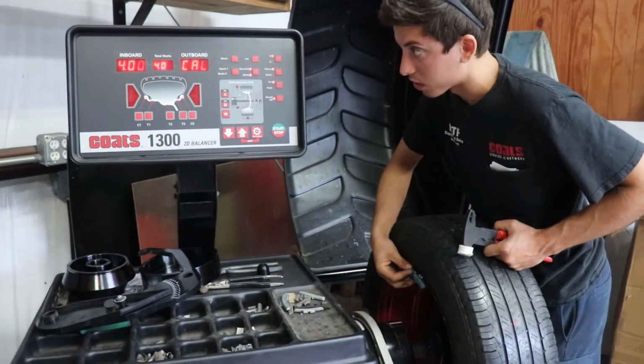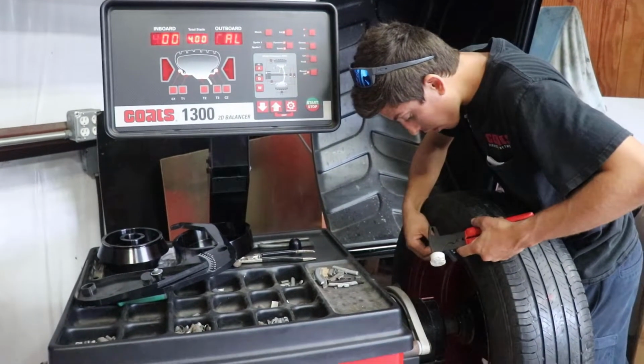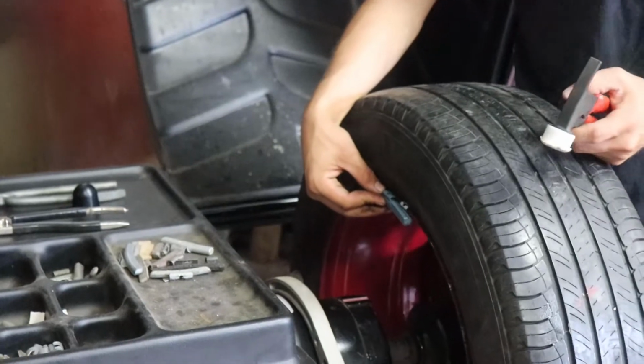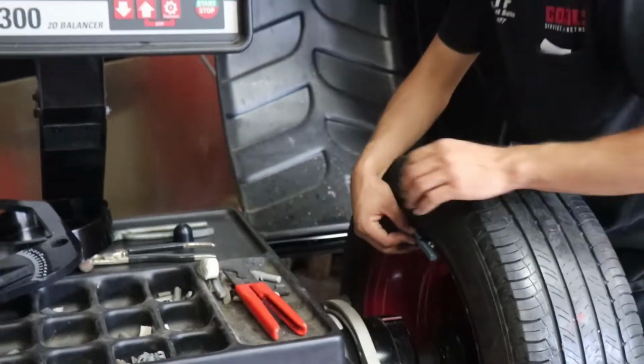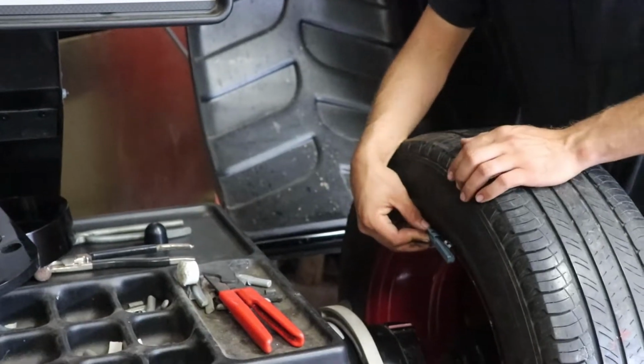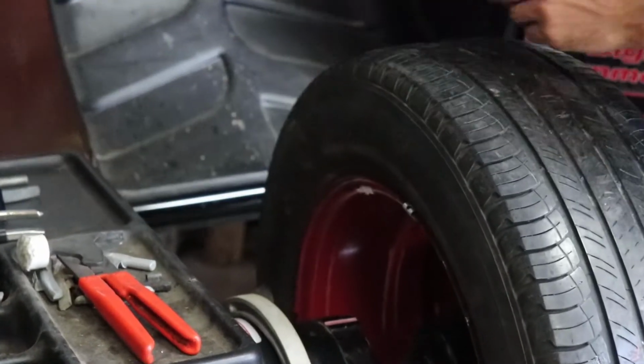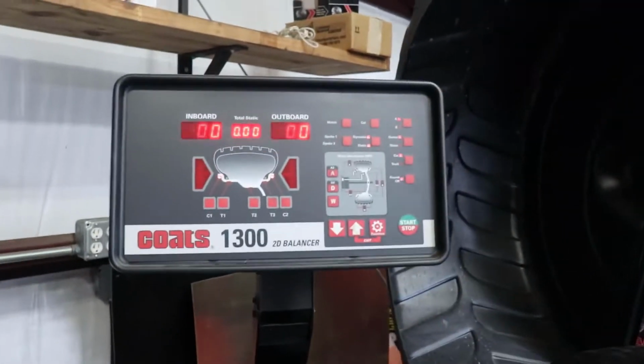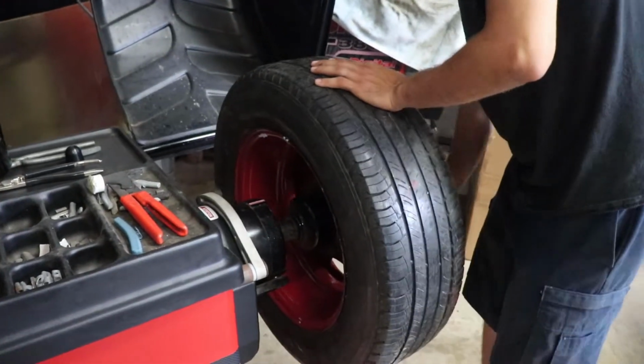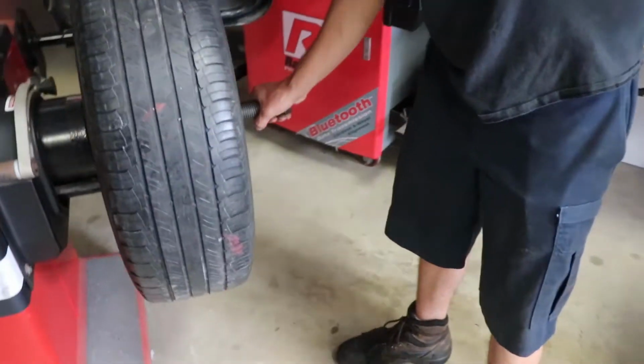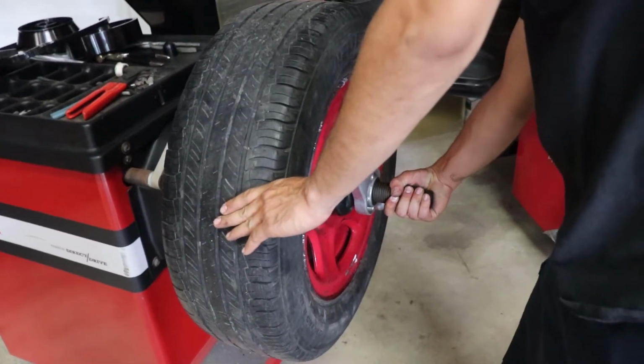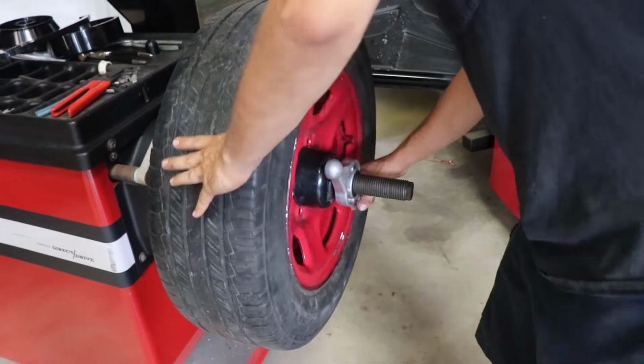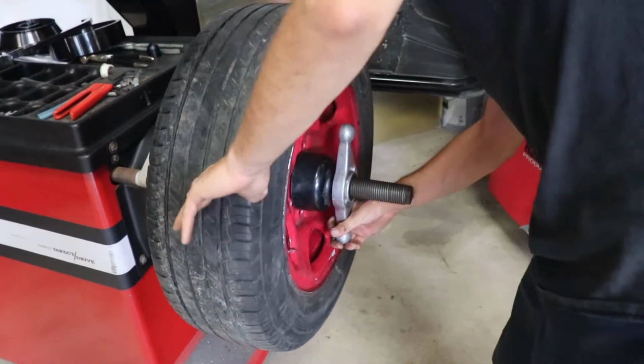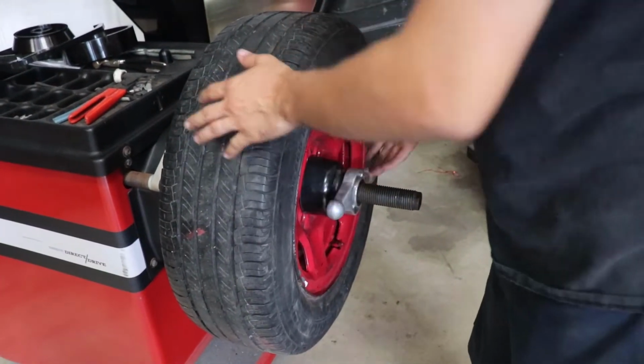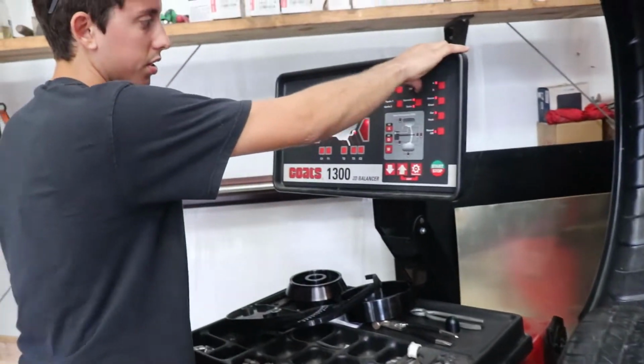Move the weight directly across the other plane. Unfortunately, this is one thing that does happen often whenever you're going through a calibration process. Top of the other weight. Yeah. Look at this. You get the weight right on top of there. So what you do to remedy that, unfortunately, you have to exit out of the whole thing. You see how these two have to exit right there. You exit. You're gonna loosen the wheel. Grab the spindle, and then just rotate the spindle. What you're doing is you're just clocking it off that axis. About a quarter of a turn. What that'll do is it'll just reposition it. So then you go right back into your calibration process.